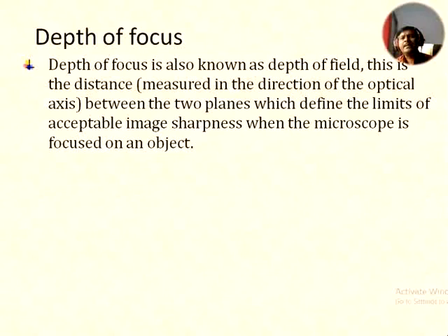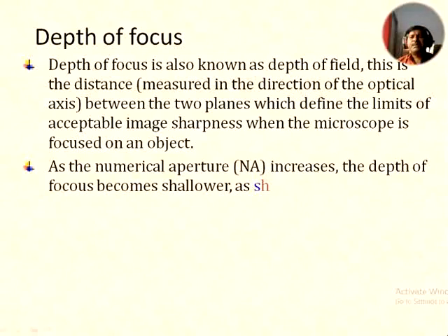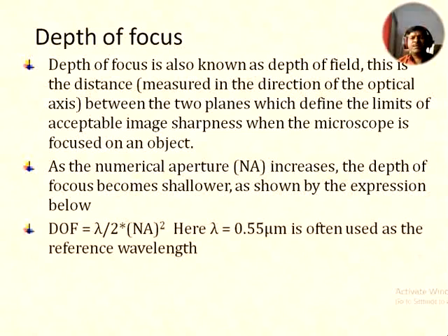By using that fine adjustment knob we can sharpen the image. As the numerical aperture increases, the depth of focus becomes shallower, as shown by the expression below. See the expression: the depth of focus, represented by DOF, is equal to lambda by 2 into numerical aperture squared.